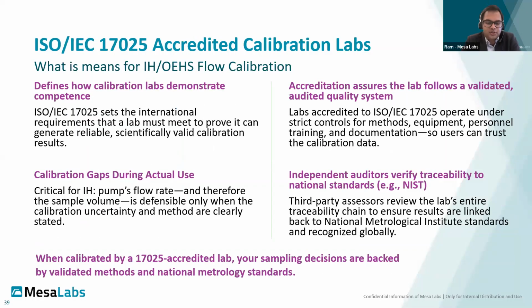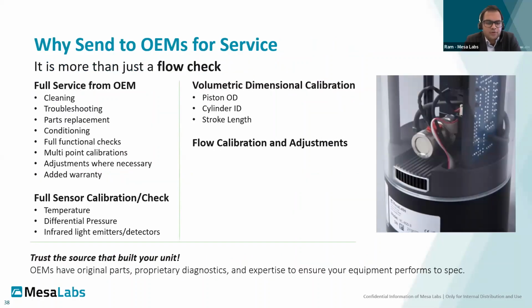For primary flow calibrators such as, Lawrence, I think you may want to move back one slide. Sorry. Yeah, for primary flow calibrators such as Defenders and DryCals, this includes verifying the very core of what goes into measurements. The glass and piston and the LED detectors that ensure gas volume and time of flight integrity are extremely crucial as part of the maintenance and recalibration process. So the take-home message here is simple: trust the source that built your unit.